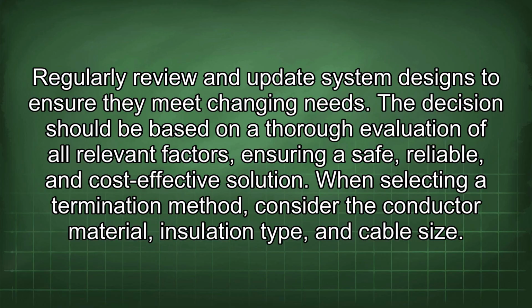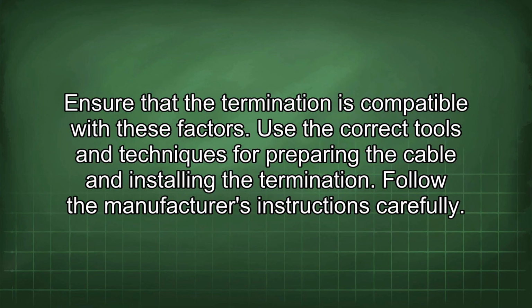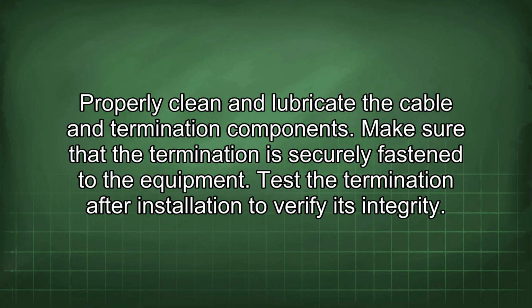When selecting a termination method, consider the conductor material, insulation type, and cable size. Ensure that the termination is compatible with these factors. Use the correct tools and techniques for preparing the cable and installing the termination. Follow the manufacturer's instructions carefully. Properly clean and lubricate the cable and termination components. Make sure that the termination is securely fastened to the equipment.